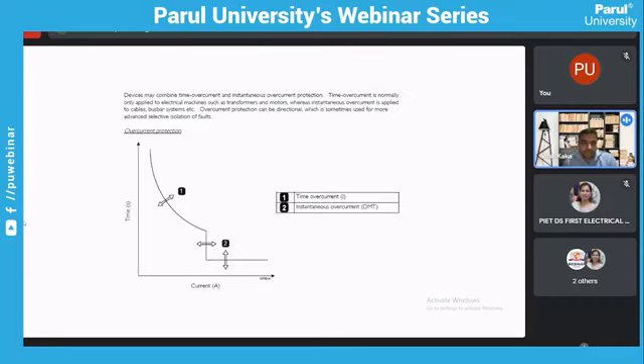This is a graph for overcurrent protection. The first one is showing a time overcurrent, where you are coordinating your relay to operate at a specific time and after a specific period of time. And point number 2, in the graph, you can see that it's not waiting. There will be only a marginal fraction of time, and your protection relay will straight away initiate an action for tripping the breaker and isolate the fault as early as possible.